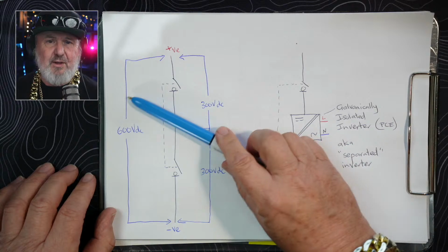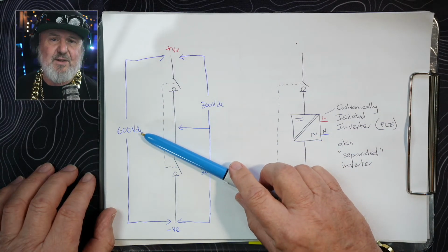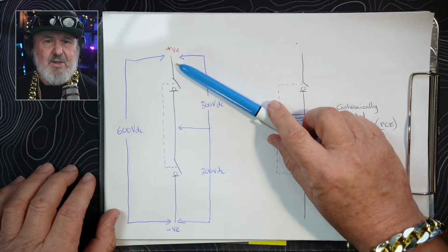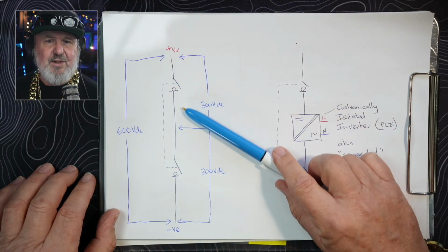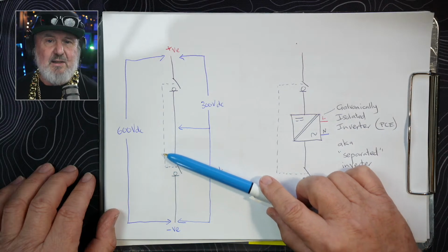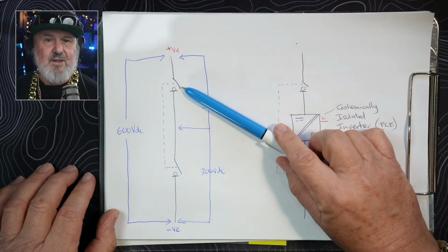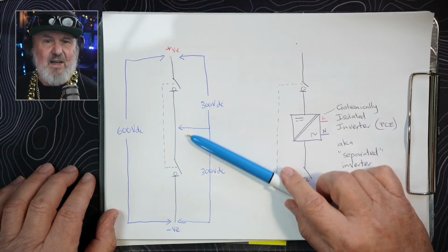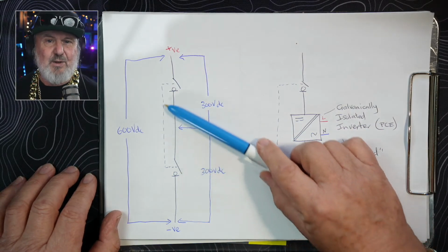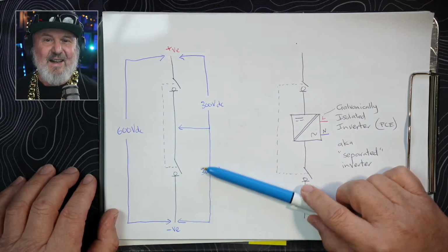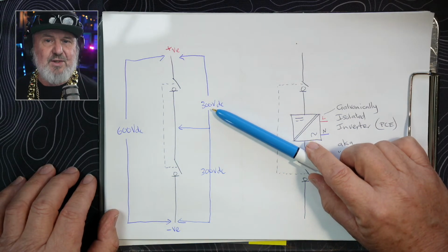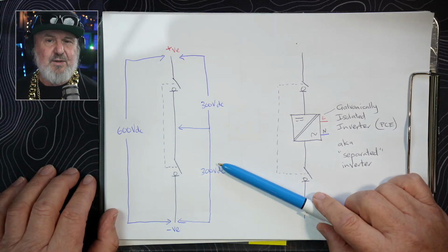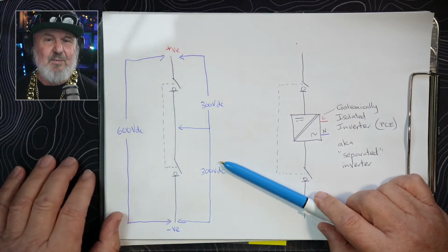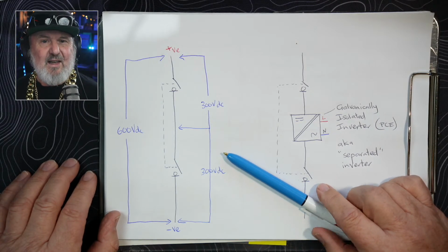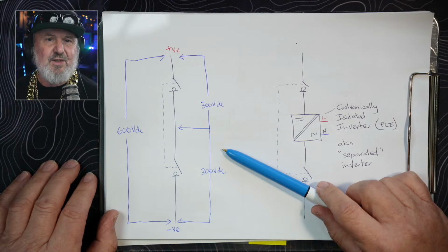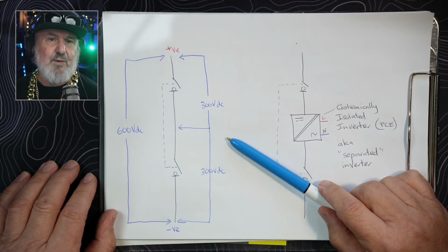So we've got a 600 volt open circuit array here, so VOC 600 volts. And in this little diagram, I'm just imagining that we're going to have two series switches, and they gang together, hence the little dotted line here. They gang together. And so when I operate this ganged double-poled switch to turn off what I'm effectively in this diagram is a short circuit, I'm going to see up to 300 volts across each switch because they are splitting the voltage equally. So this is explaining how putting switches in series reduces the switching voltage across each switch mechanism, what we often refer to as a pole.